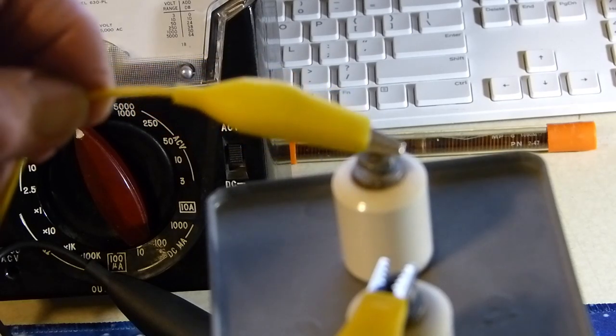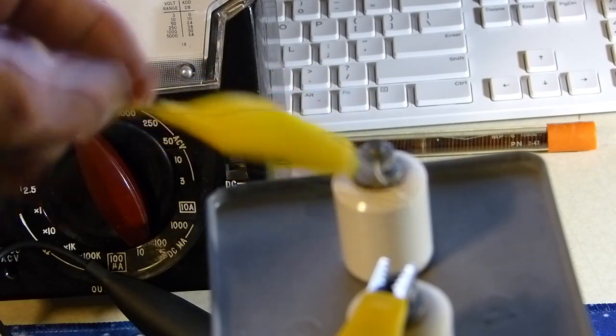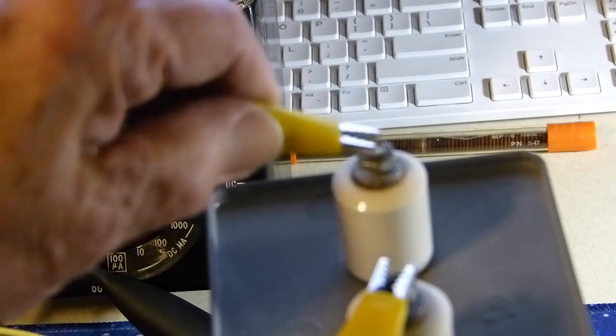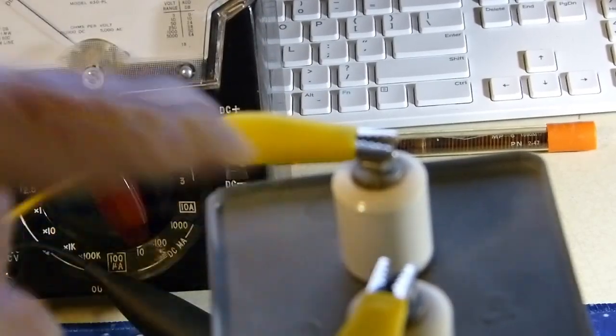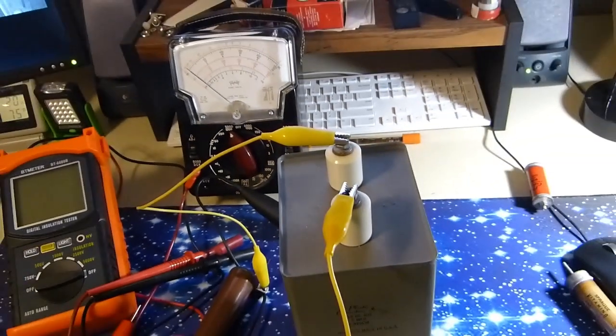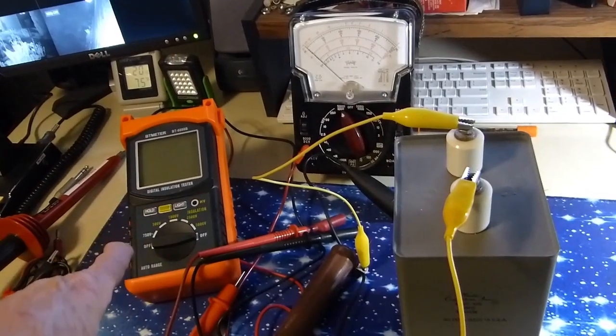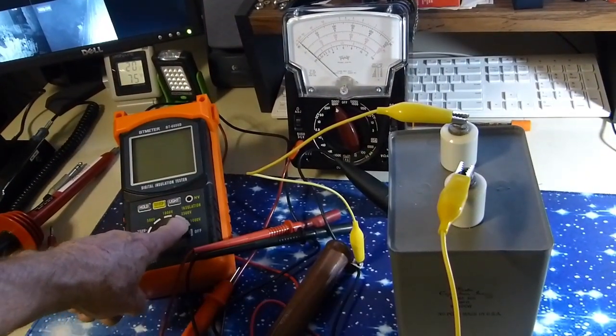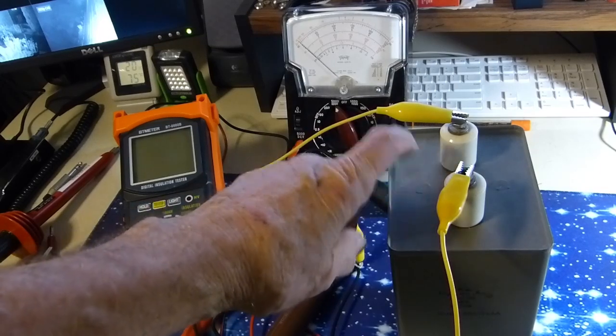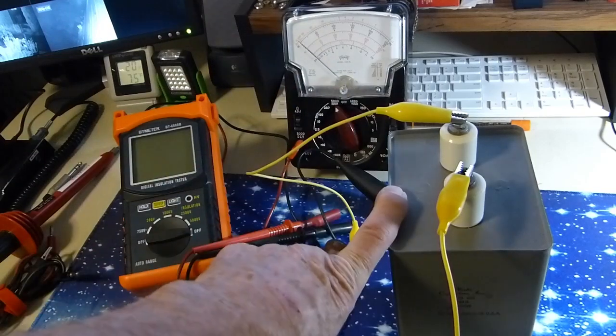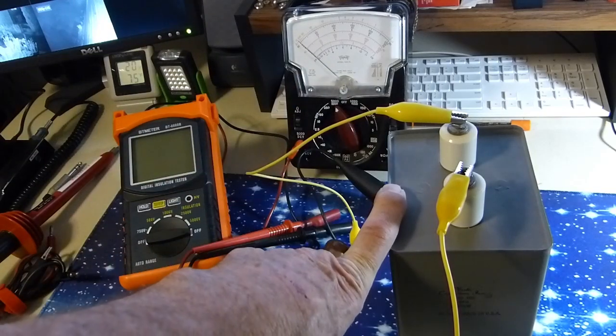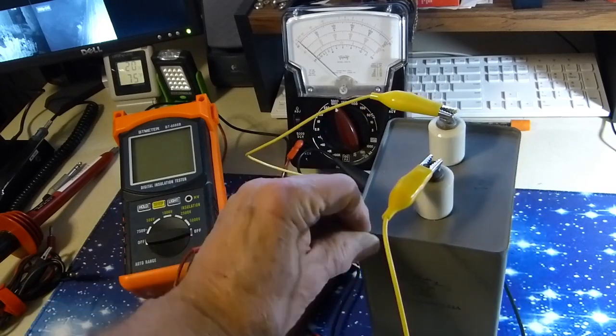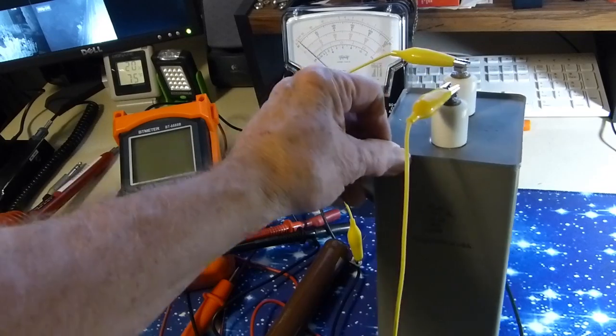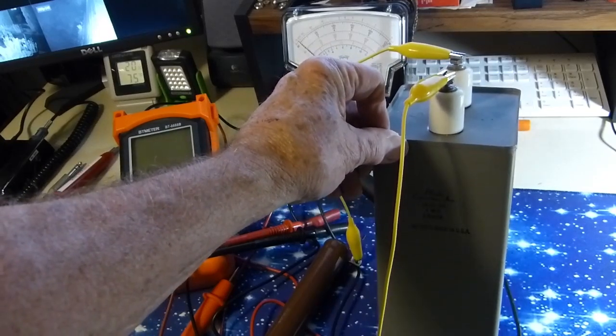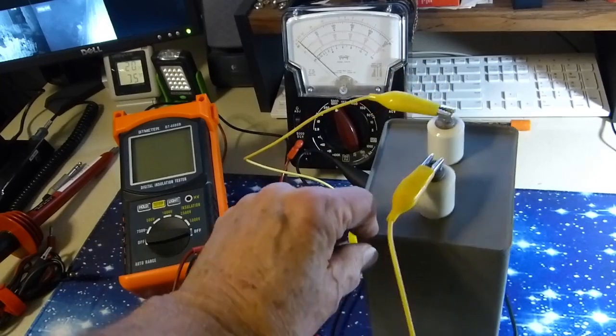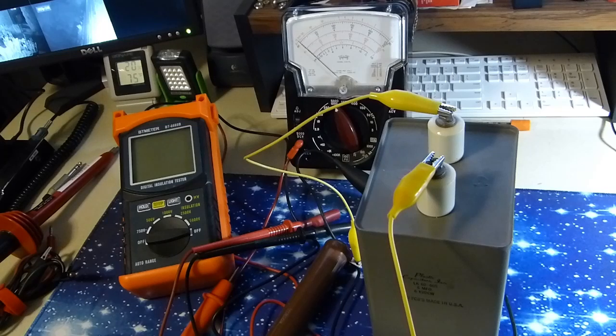Now, the point is, that's through a 100,000 ohm resistor, so it's bled off pretty well by now. But if you got across that thing right there being charged by this little device over here, which puts out 500, 1,000, 2,500, or 5,000 volts, you can charge this guy up to a charge that is absolutely deadly. A capacitor of this size, 6 microfarads, handles up to 6 kV, and is as deadly as a turned-on power supply if you get across it.